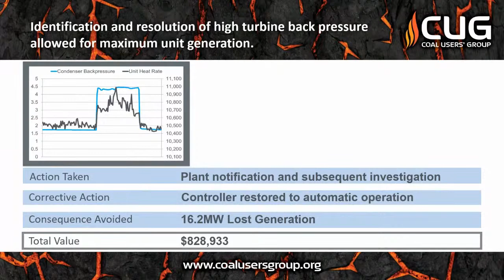We had statistical models and other rate of change alarms set just below the settings in the plant control rooms. The POC contacted the plant control room, and the plant did investigate. They found that a valve had failed open due to a failed controller card.